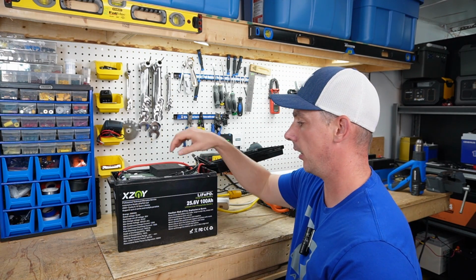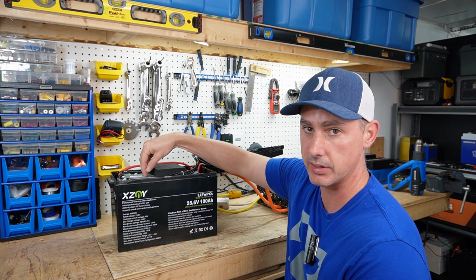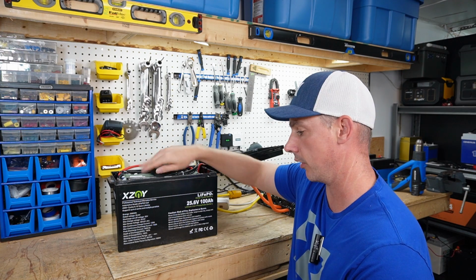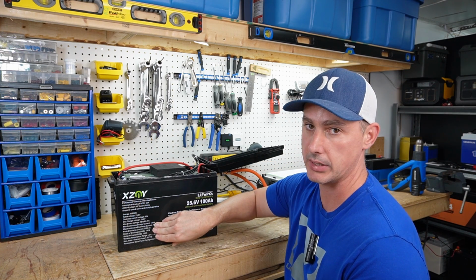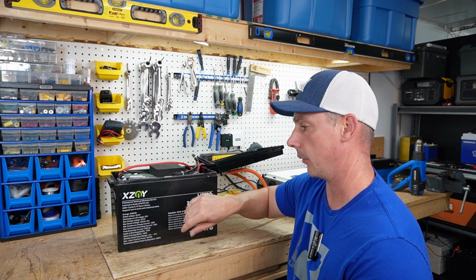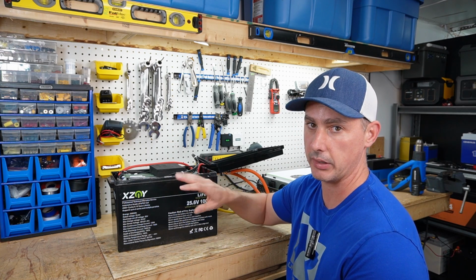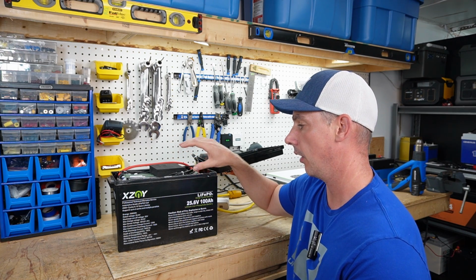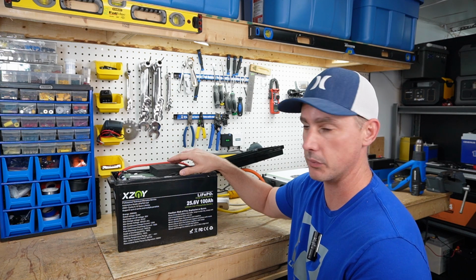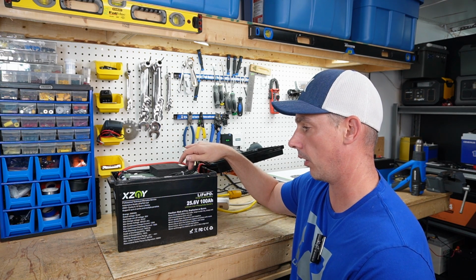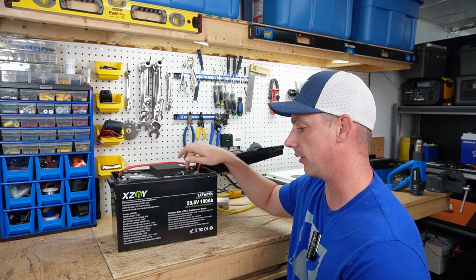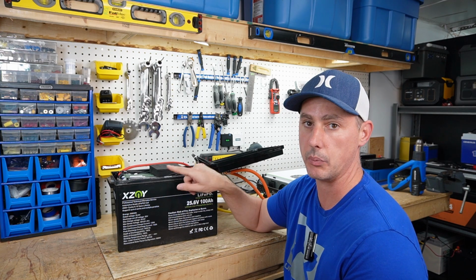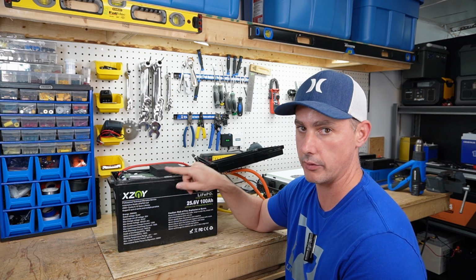The BMS rating - on the BMS itself it's saying 100 amps charge and discharge, but then the rating on the battery is saying 120 amps. Now we did do about 15-20 minutes, more or less 20 minutes, of a discharge at 120 amps, and the BMS started to get warm on the heatsink. It's not ideal, so I would stick to what the BMS says and try to just do 100 amps of discharge continuous.